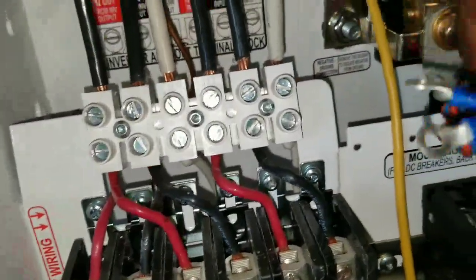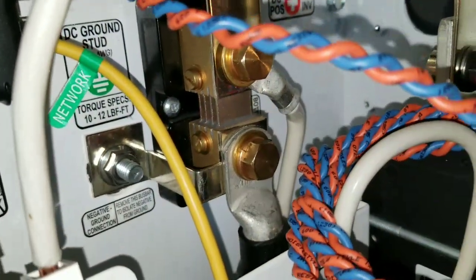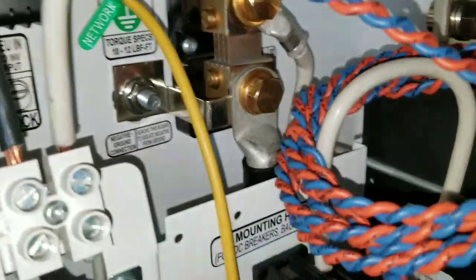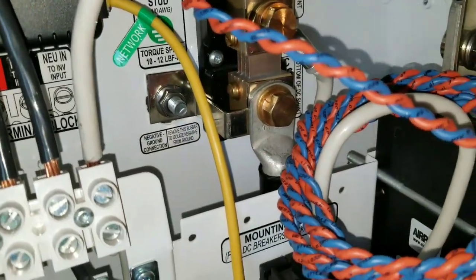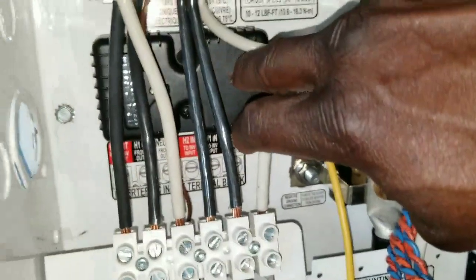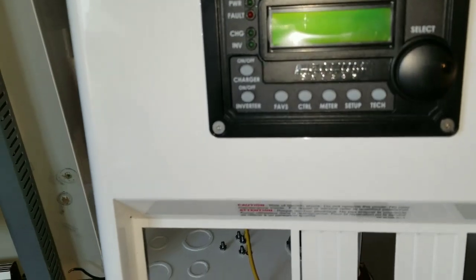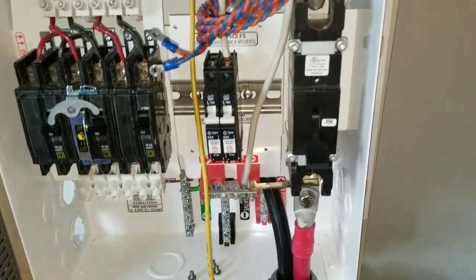These two wires here are the sensing wires; they're gonna go right on the corner at these two terminals. This sensing wire takes the measurement from the shunt — how the load or power travels — and it reads it, sending it to this box, the battery monitor kit.